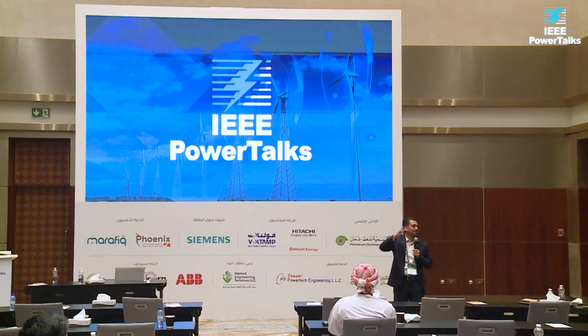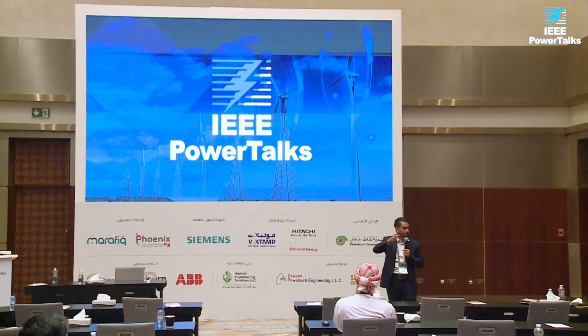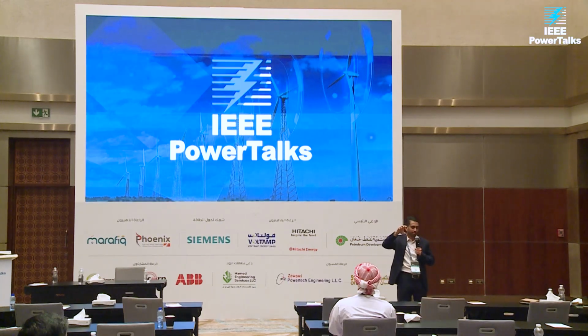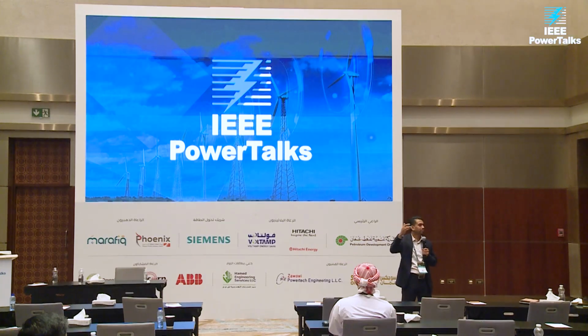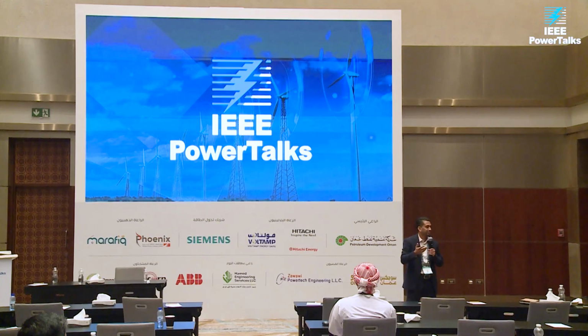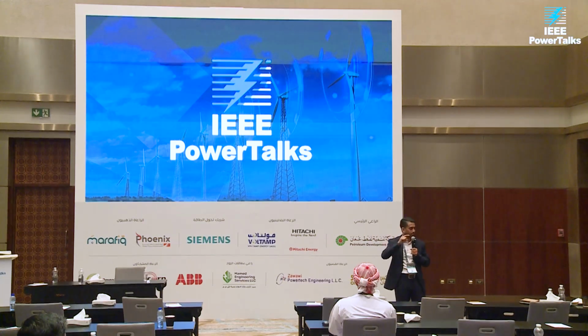Then it has a branch. It goes on the left, on the right, to different places. And then when there is a fault, like let's say a tree falls on the line, this will be a permanent fault. But let's say a bird shorts the two lines. It's a temporary fault, but the station will still operate, right? The primary station will still operate. Now you need to know if it's a temporary fault, then you can immediately restore the power, right? You don't have to wait for somebody to go through the whole network and ensure that it's just a temporary fault. So you want to restore the power to the consumer faster.